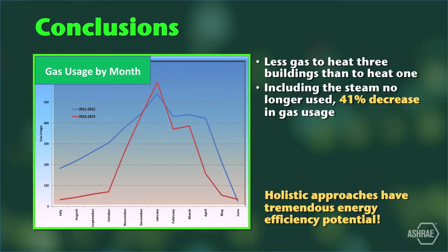Here's the same results graphed by month. The blue line is the gas used at science by itself before the project. The red line is all three buildings after the project. Including the steam no longer used, which isn't shown on the graph, there was a 41% decrease in gas use. One month in the middle of winter, we did use more gas than the previous year, but again, heating three buildings instead of just one.